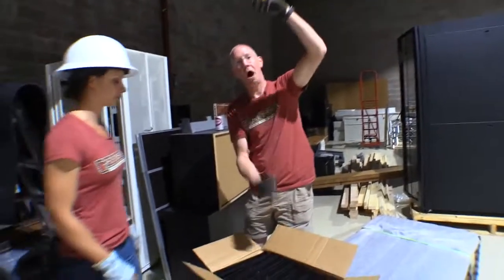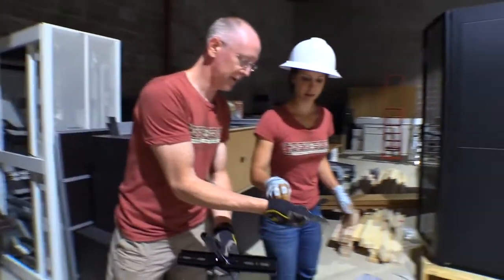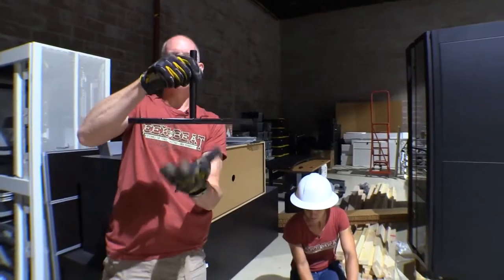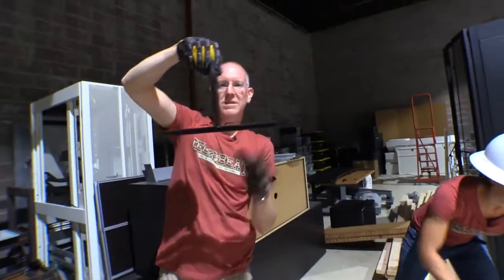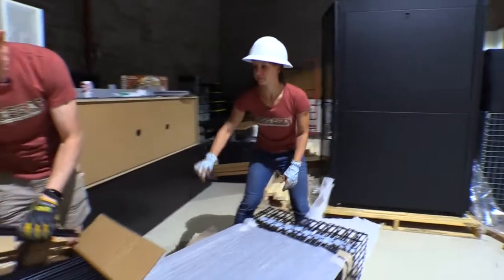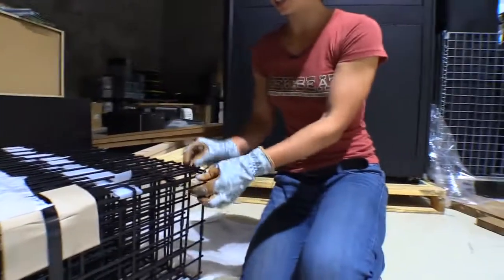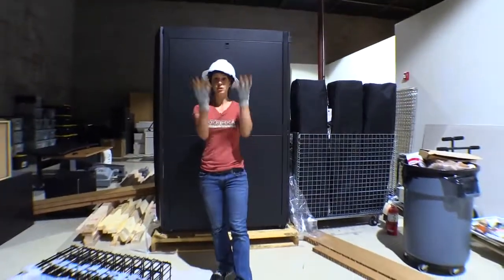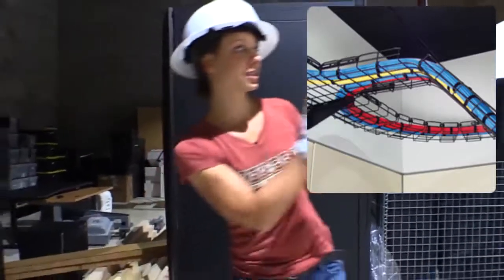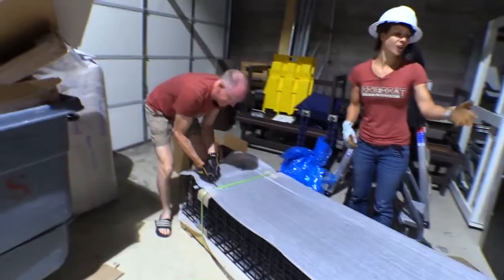What we're going to do is get some drop-down threaded rods, and these are the support systems. What will happen is the channeling will be suspended from the ceiling and the threaded rods will come down from the ceiling and hold the basket. Then you run the cable through the basket. That's a lot of these. So basically, you can see one of these — just imagine this piece here. There are two together. So that would go up on the ceiling with those connected to the ceiling, and then all of our cables routed across the building. It's going to be awesome. I really want to get one of these out so you can see what they look like.